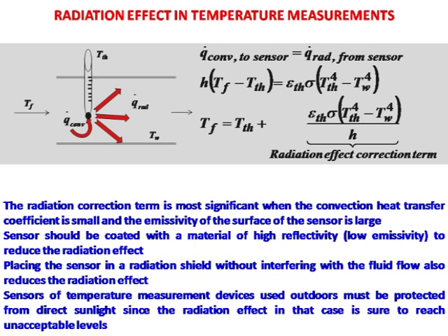When will the fluid temperature be equal to the thermocouple temperature, or the other way around? When the heat transfer coefficient is very high. Only for high speed flows. High speed means not a very high speed. What I mean is when the velocities are reasonably high, for example, air velocity around 3 to 4 meters per second, the heat transfer coefficient between my thermocouple and the fluid flowing over the thermocouple is high.